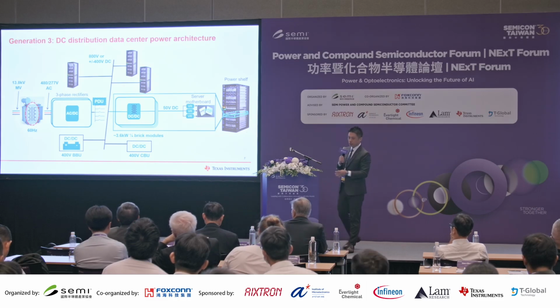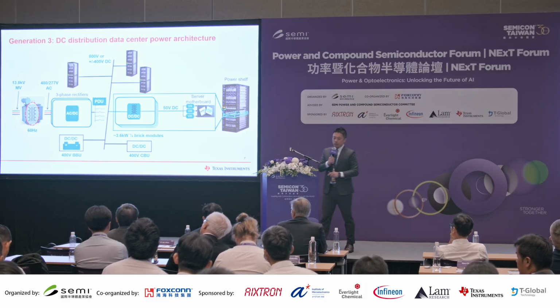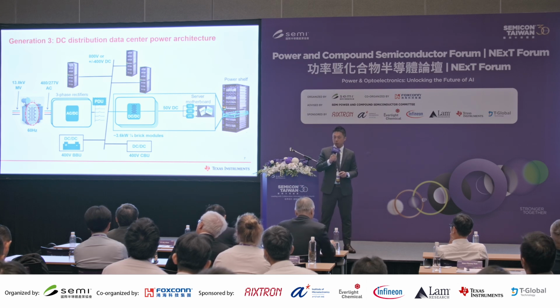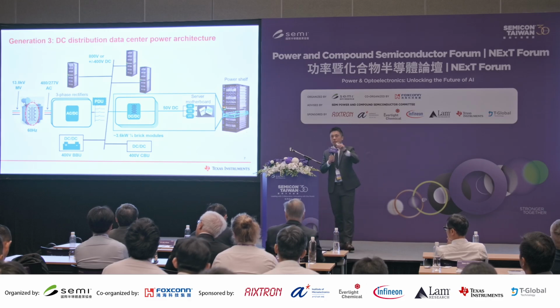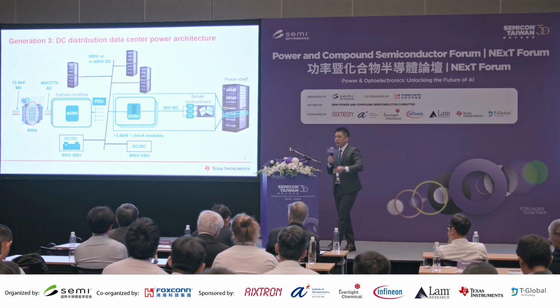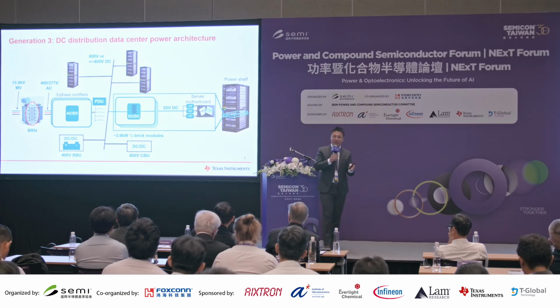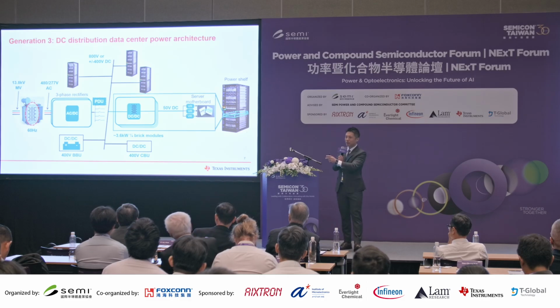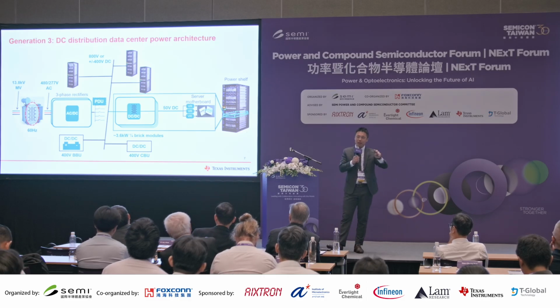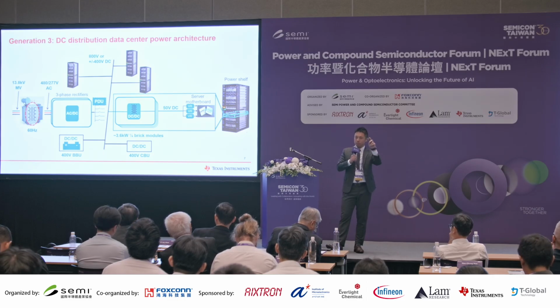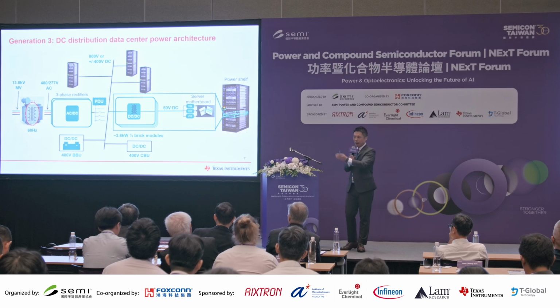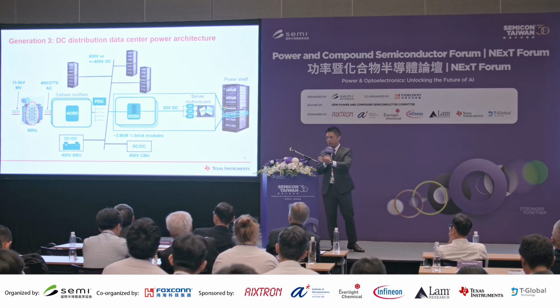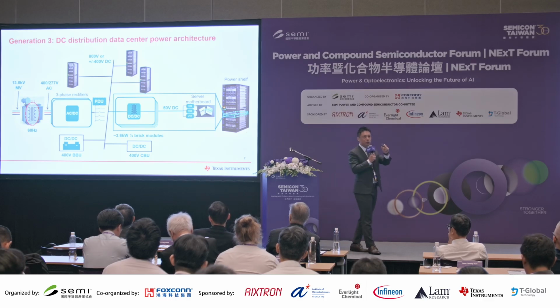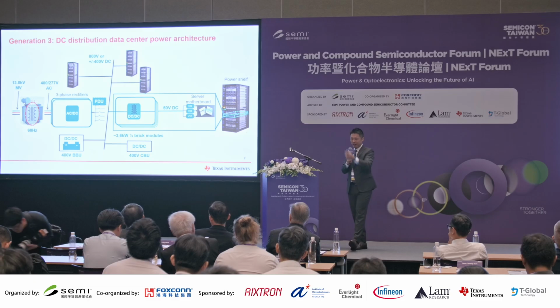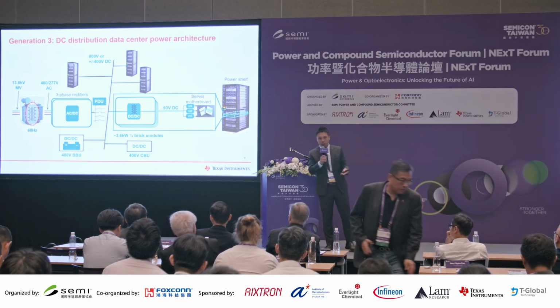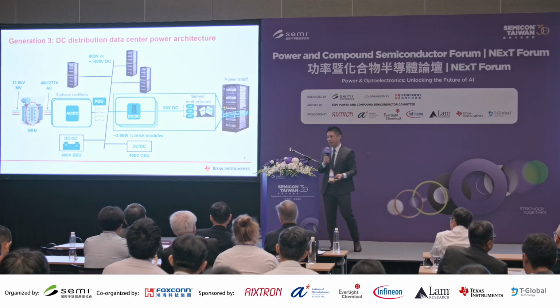So people start to think about the next generation, and here you see a couple of changes from our genius engineers around the world. One, as the density of CPU, GPU, and networking switches starts to occupy the entire rack, the big and bulky power supply is pushed out of the IT rack. So there's the idea of a sidecar, an independent power rack, running DC power from the sidecar to supply each IT rack. If you still run at 50 volt DC voltage, from the quick calculation it equals 200 kilograms of copper weight on the rig, making it physically impossible to use 48 volts to support 1 megawatt or even scale further in the future.